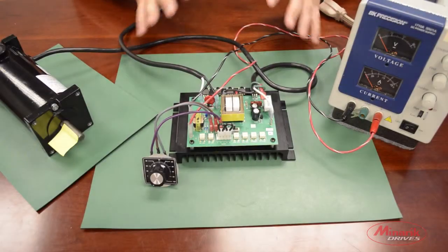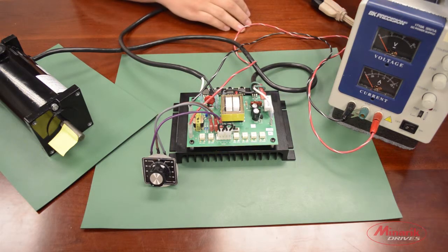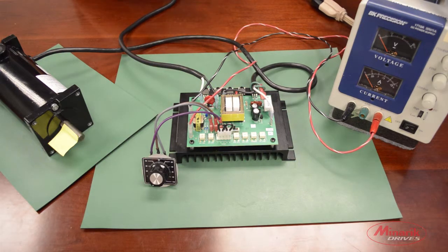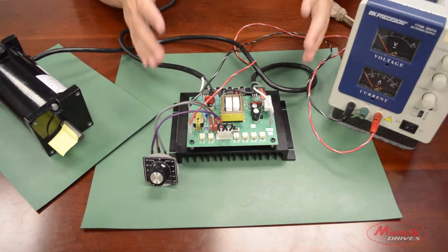Now we have the drive in signal with ratio output mode. While in this mode, the input voltage signal will set the max speed reference and the speed pot will set the ratio at which the drive will see that speed reference.